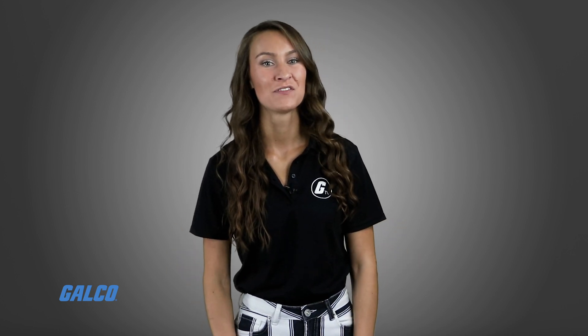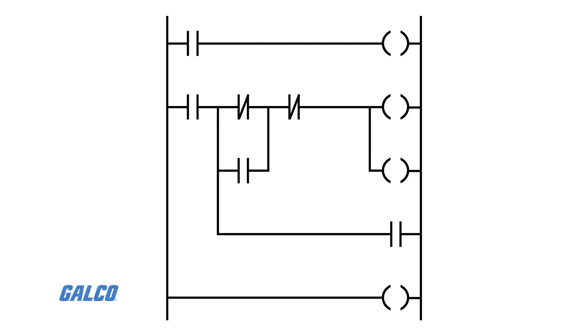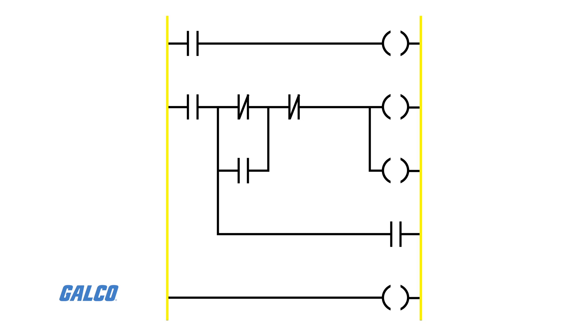Like the old ladder diagrams that it is based on, ladder logic's visual design documents how connections between the devices are made. They are called ladders because they are constructed in a way that resembles a ladder, with two vertical rails and rungs in between them. On the left is the positive power rail, which flows to the negative power rail on the right through physical devices that are connected on the rung.